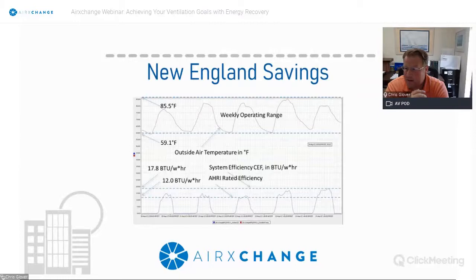For the most part, these devices are reliable. They want to spin, and if you have a good maintenance regime in place, and I think maintenance regime is a double-edged sword. A lot of people think I have to do a ton of maintenance to these things in order to keep them operating, which isn't the case at all. But I like to say proactive monitoring of these devices. A little bit of legwork in terms of making sure that they're remaining clean and they're spinning and everything else is in order will go a long way enhancing the life expectancy of these devices, which in my experience is usually between 15 and 20 years is where we typically see these devices starting to reach their end of life expectancy.